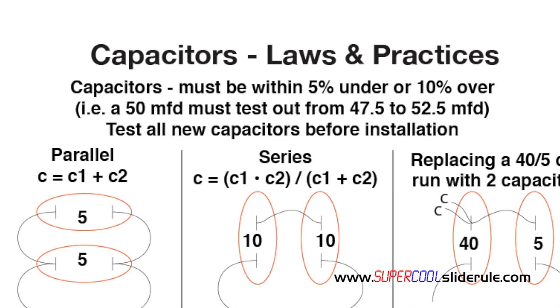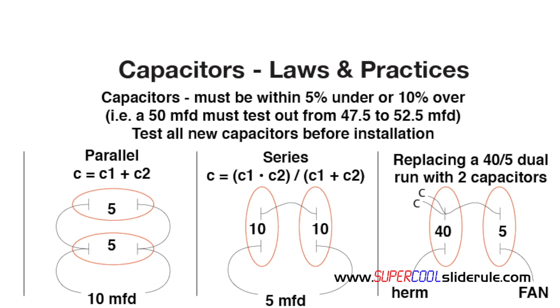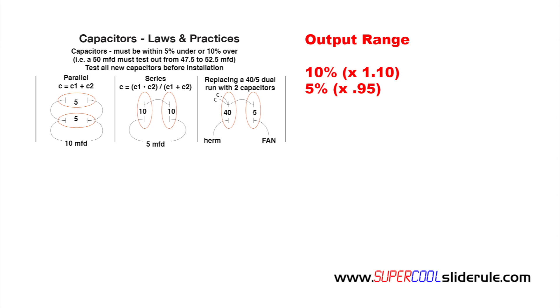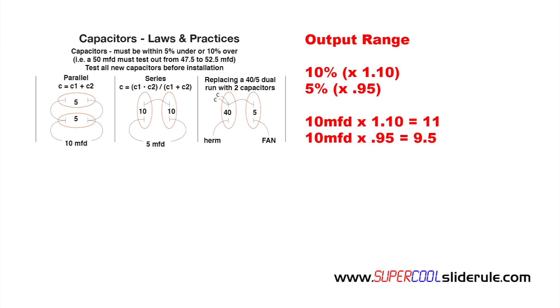The output must be no less than 5% under or 10% over. Here is the math: for 10% over, we multiply our capacitor rating by 1.10, and for 5% under, we multiply our capacitor rating by 0.95. So 10% over is 11 and 5% under is 9.5.